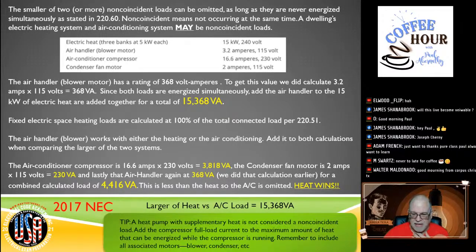Now, I will remind you right here, here's a little tip. I like to throw these little tips out to you. If you're dealing with a heat pump with supplementary heat, it's not considered a non-coincident load. Add the compressor's full load current to the maximum amount of heat that can be energized while the compressor is running.